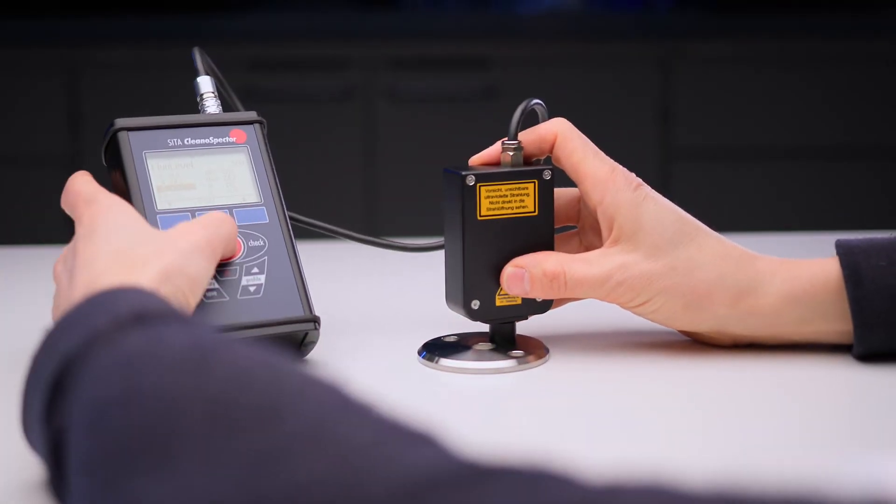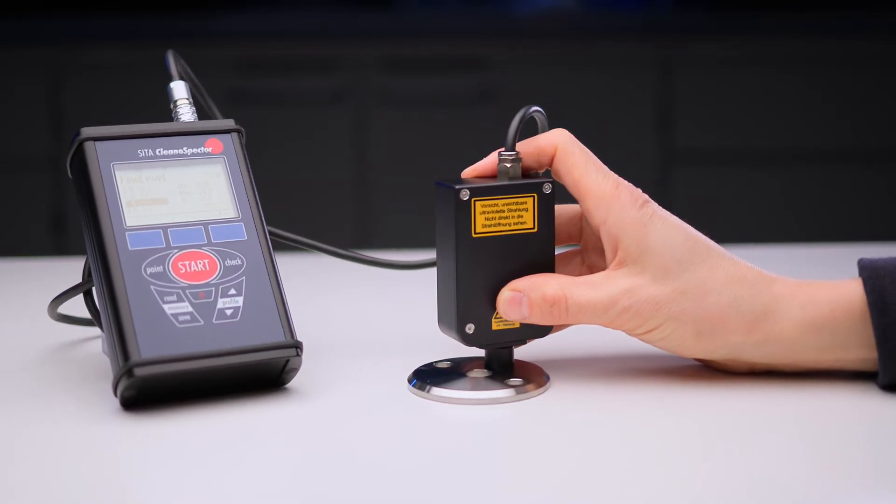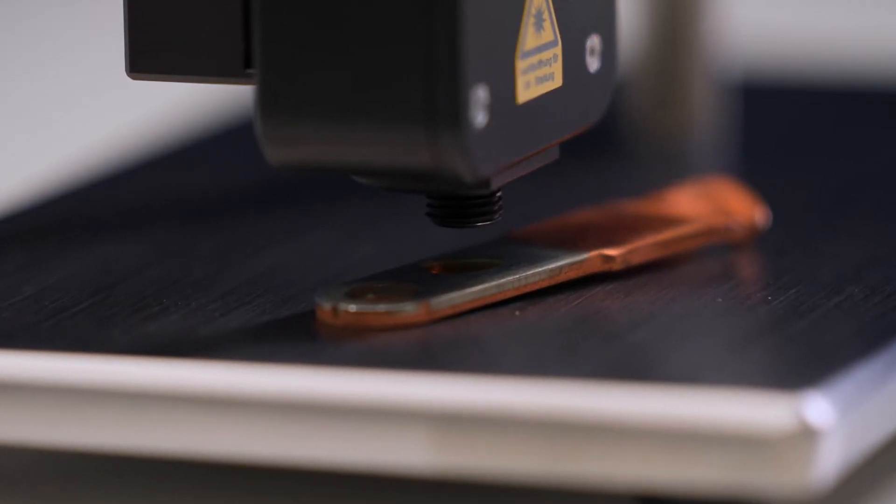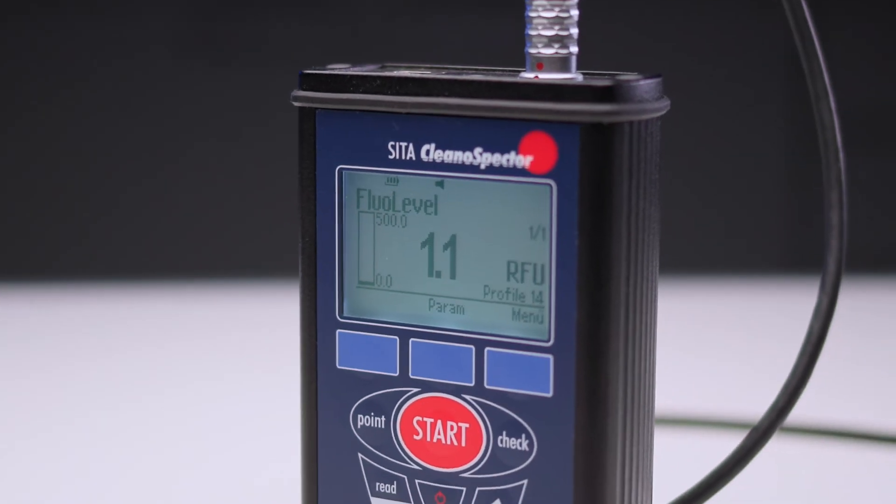The SITA CleanoSpector is our measuring device for checking the cleanliness of metal surfaces or monitoring anti-corrosion oil or primers. At the touch of a button, it provides fast results directly in a manufacturing process. The SITA CleanoSpector excites with UV light and measures the emitted fluorescence. The lower the measured value, the cleaner the surface.